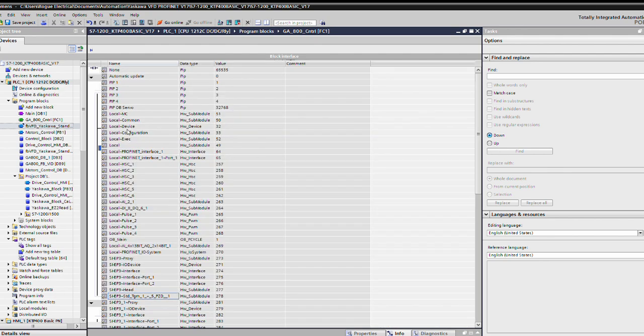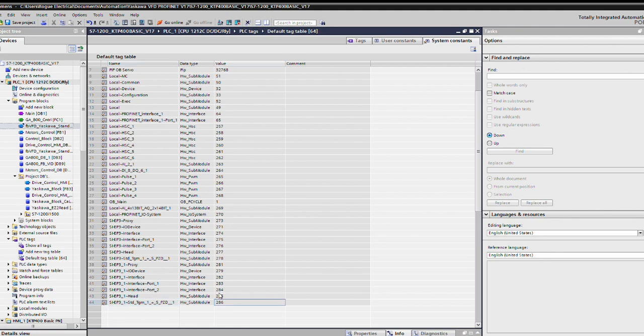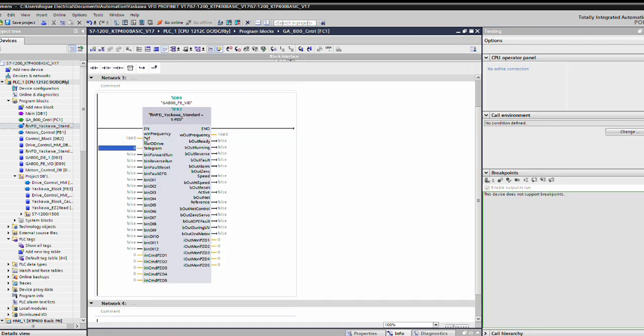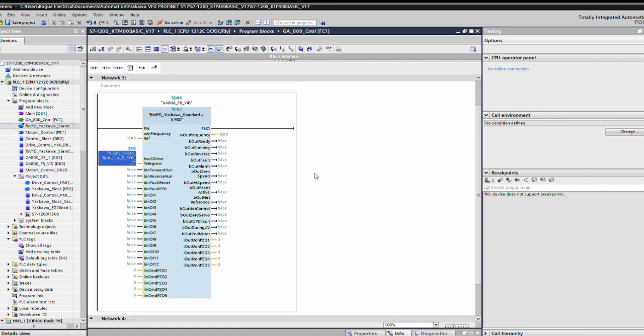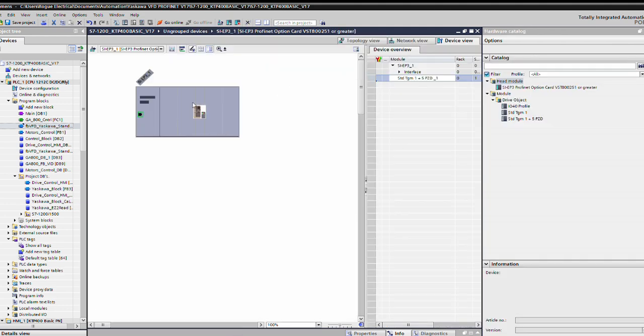Now let's go get that telegram. I'm going to go to default tag table. Now let's roll on down. What you're going to notice is that you have your standard telegram right here. It's going to be module number 286. Previous one I used was number 278. So what we're going to do, we're going to take that, copy it. Then we're going to come over to our control, go hardware telegram, and paste that in there. Now it knows it's number 286. It's pretty smart, isn't it. Now we're going to go back over here. I'm just going to have a look at it so you all can see it. And this is about all hooked up.